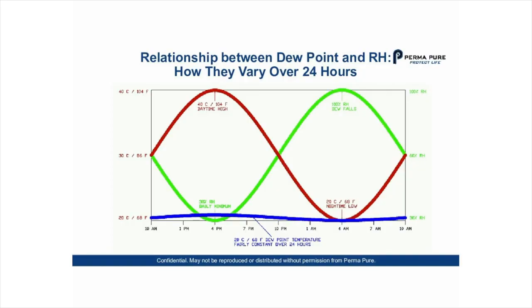Anybody working with measurement equipment outside will see that in many cases you might have dew that covers everything every morning. This could be detrimental to your measurements and your equipment. It also makes it very difficult when you're measuring particles, as the particle size is dependent to some degree on the relative humidity. This constant change in temperature and relative humidity makes any type of atmospheric measurement very difficult unless you try to correct that by drying the sample or keeping the sample at a constant relative humidity.